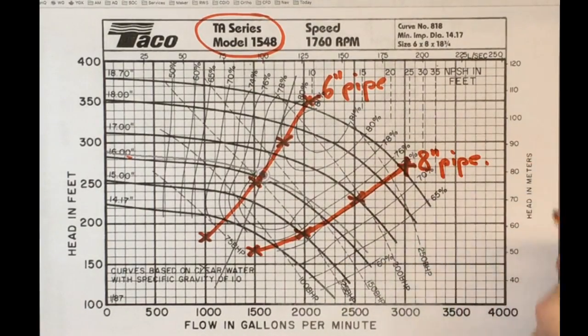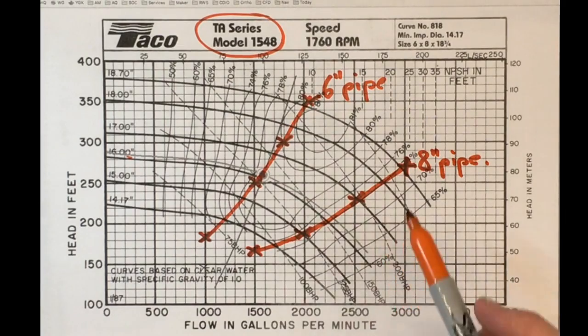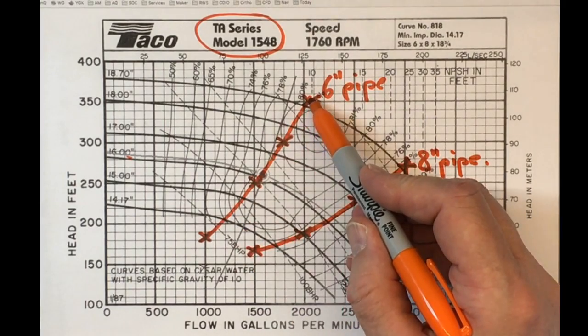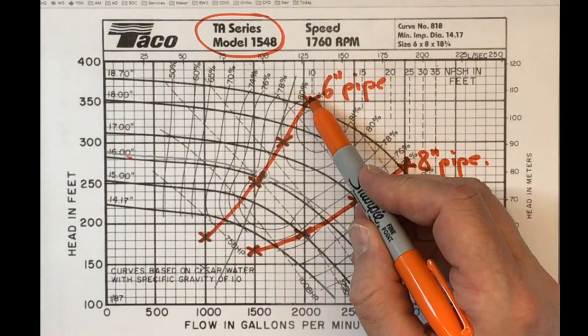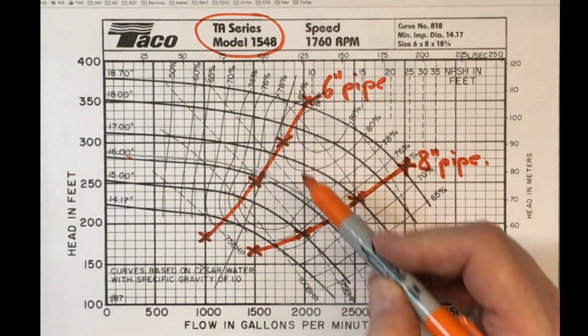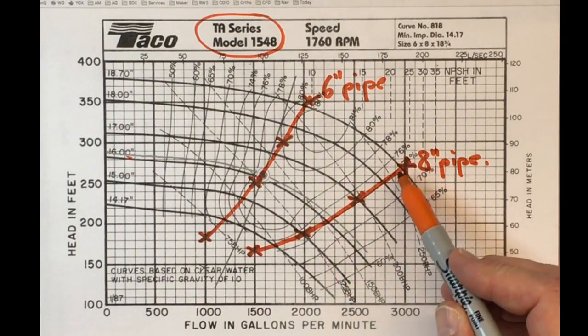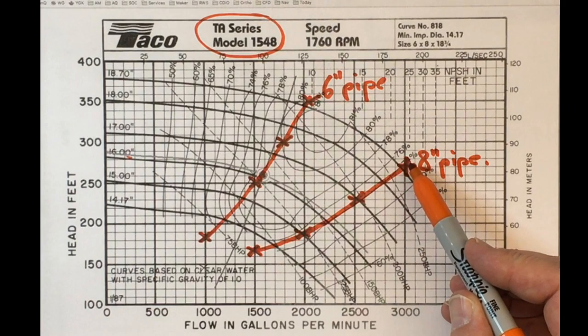So now we're trying to pick between two different design conditions. One is this 6-inch pipe where just about half of the energy we were putting in was going into friction losses in the pipe, and the other is this 8-inch pipe where it's a much smaller fraction of the energy that's being thrown away.